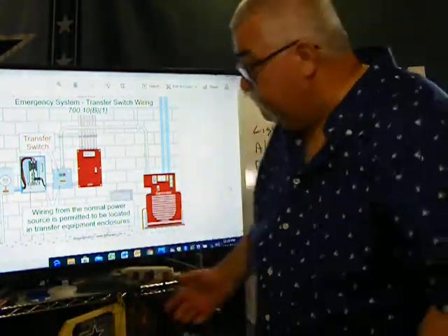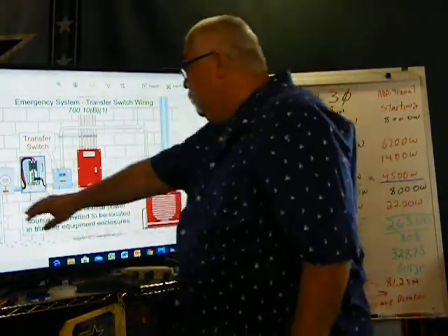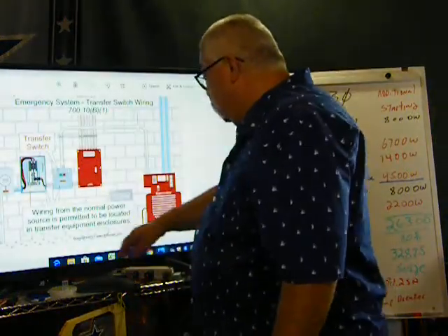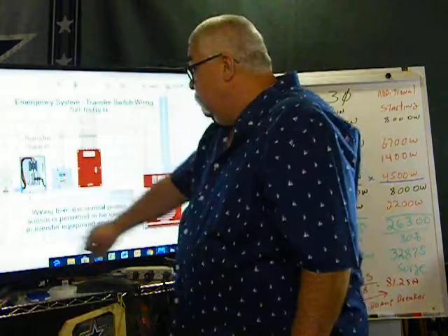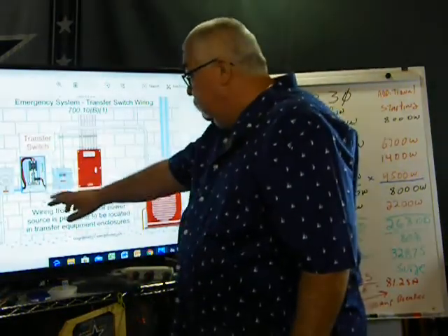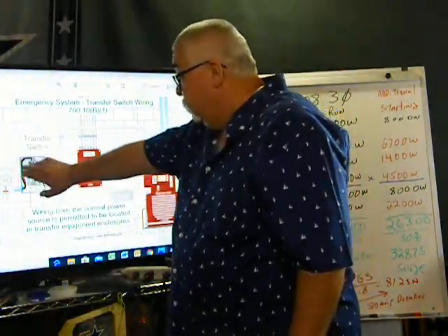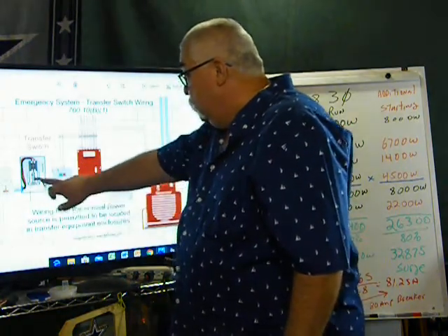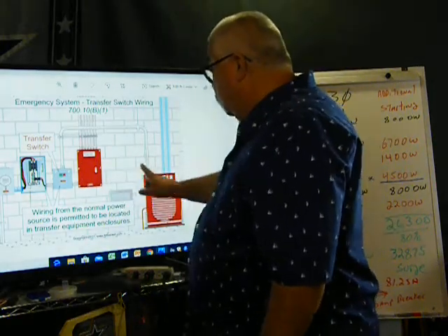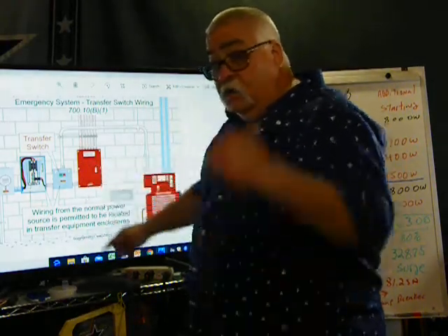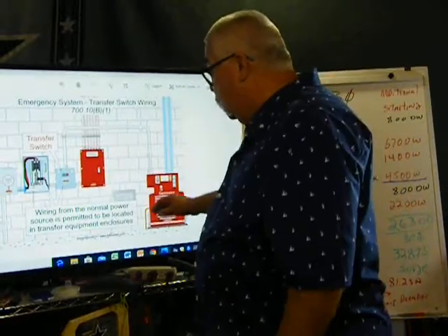That's a drawing coming off of Mike Holt's website. So here's the generator going to the panel. Again, you can see these wires look bigger than these little wires going here. So this only has to carry what's in here. This generator only has to provide power for what's in here. I got a little job behind me to size that generator.